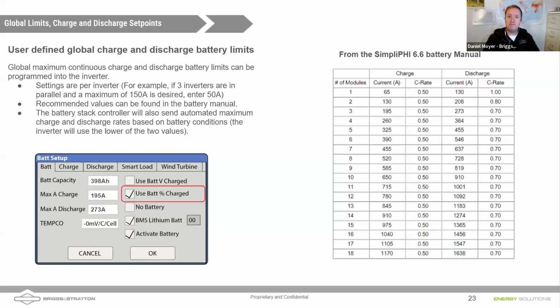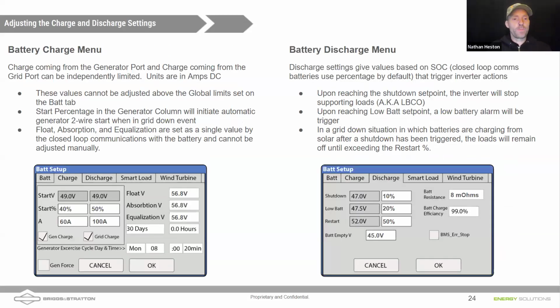It's right there. Yep. And also to point out that most batteries, so those are for lower voltage batteries, it'll do a higher amount of power, so it can do more current. But for a 48-volt battery, the maximum current that you're going to see is going to be more like 250 amps, right? Because it's limited to 12 kilowatts of power.